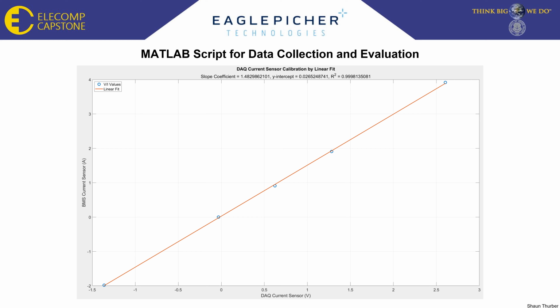The script detects the transitions in current and saves all data at each of those points, automatically deriving a conversion formula for the DAQ current sensor that also accounts for the voltage offset based on the data present in the log files. In the future, it's recommended to add a burden resistor in series with the wire to the battery pack to get an accurate reading of the current, which would help in calibration of the DAQ current readings.